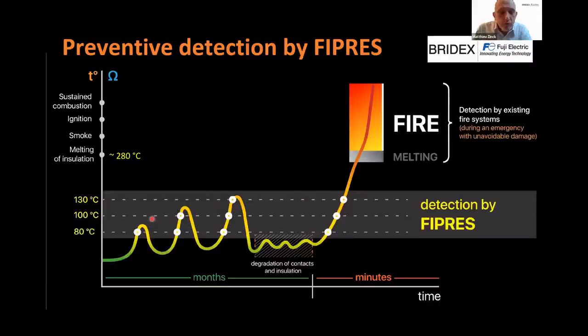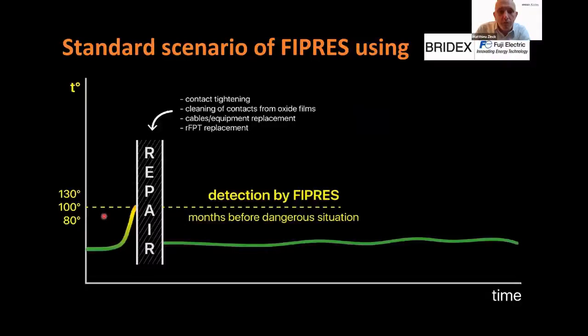A few important points to understand how FIPRES is secured is first, by understanding that the real fire really starts rather above 200 degrees and not at 100 degrees. At 100 degrees, you have a degradation of contacts, but you do not have fires. And that's the point of doing prevention at this temperature and monitoring carefully this temperature, because at this stage, it's possible to repair. And this is precisely what FIPRES allows you to do: at a temperature of 100 degrees or even before, so months before the dangerous situation, you are able to repair your equipment.